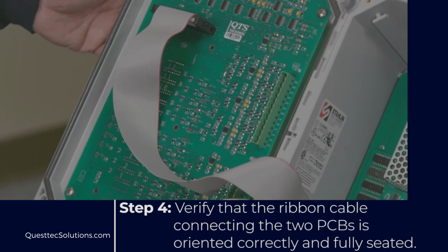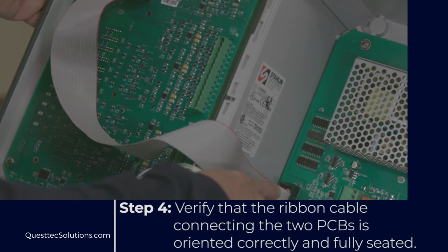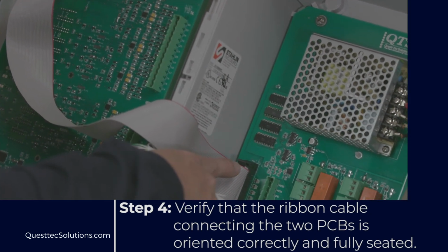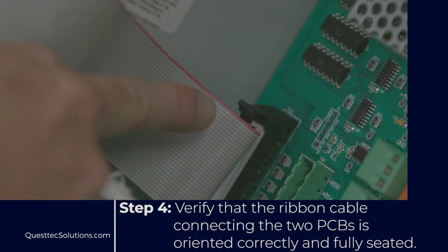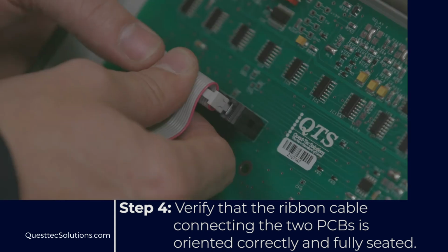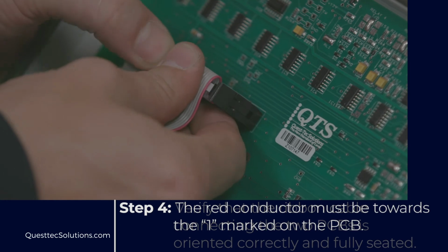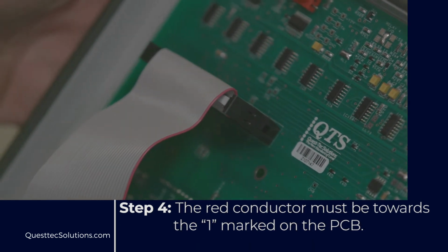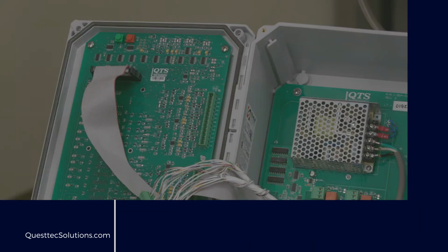Step 4. Prior to initially powering up, verify that the ribbon cable connecting the two PCBs is oriented correctly and fully seated. The red conductor must be toward the 1 marked on the PCB.